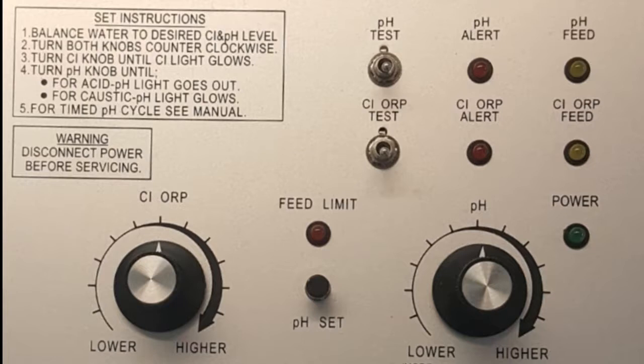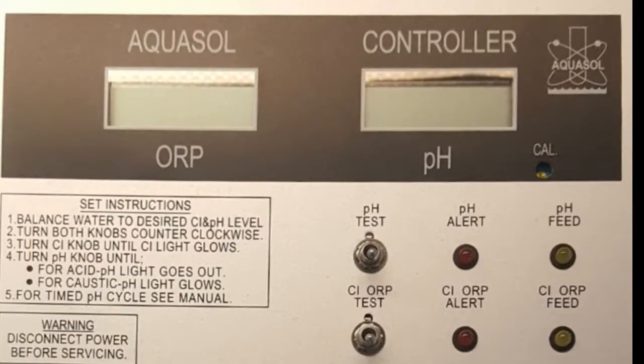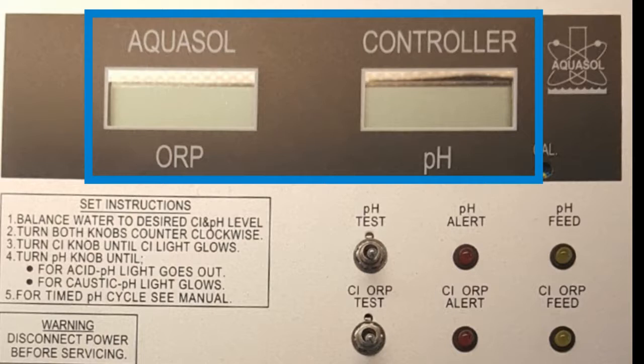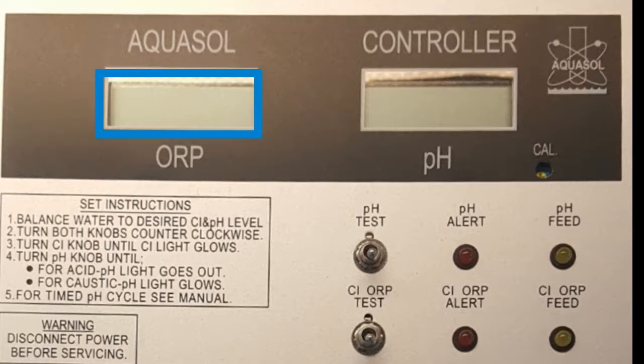Next, we have your pH set button. This is used in conjunction with the pH control knob to calibrate when you're using the pH timed monitoring feature. That's a section on the dip switches. Next, we have the meters. You have 2 individual LCD meters continuously displaying ORP and pH readings. The ORP is a millivolt reading.